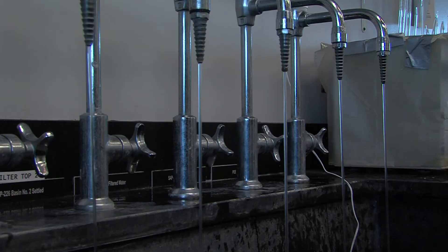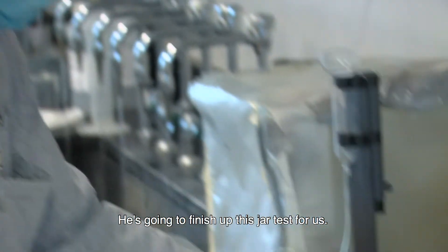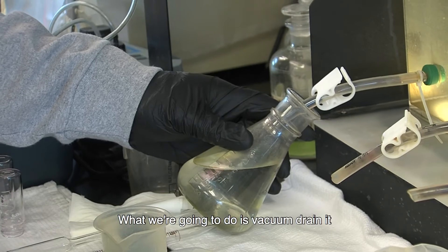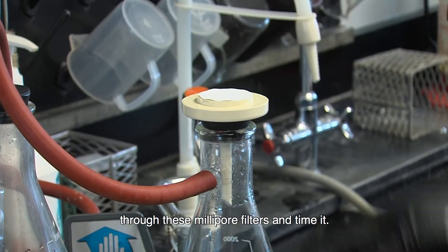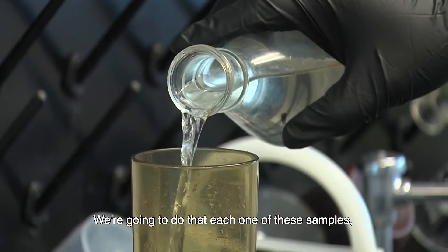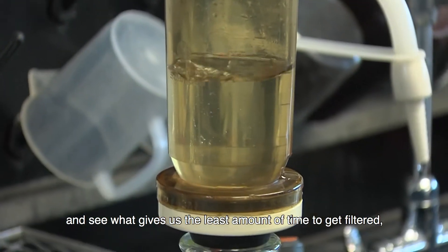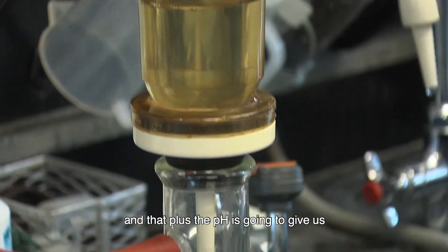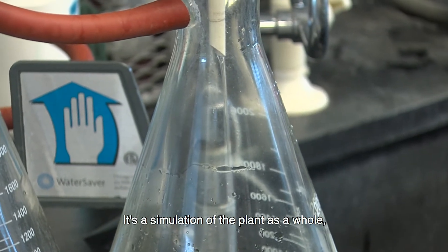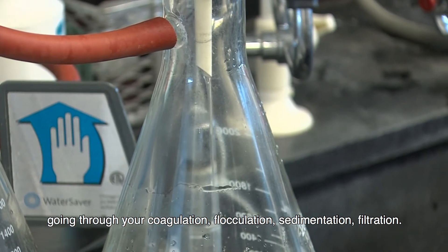Let's take a quick trip back to the lab and check on our jar test. This is Johnny Duckett, he's one of our operators, and he is going to finish this jar test up for us. What we're going to do is vacuum strain it through a millipore filter and time it. We're going to do that to each one of these samples and see what gives us the least amount of time to get filtered. That plus the pH is going to give us the optimum dosage to use. It's a simulation of the plant going through your coagulation, flocculation, sedimentation, and filtration.